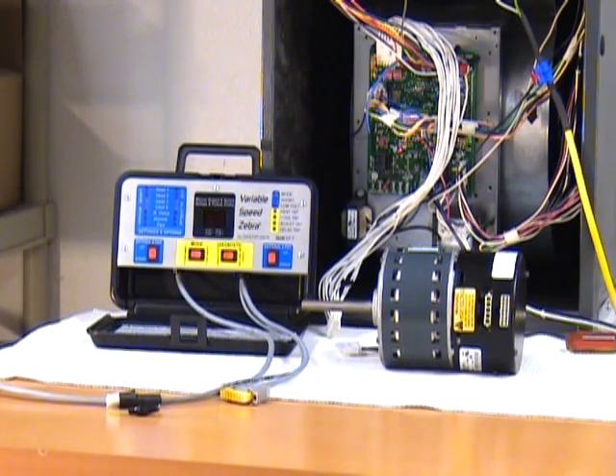GE makes an inexpensive tool, well, it's not terribly inexpensive, it's about 80 or 90 bucks, that just plugs into the motor. You hook it up and you turn on a switch, and they say if the motor runs on this one speed, the motor will probably run okay in all the other speed settings too, but they don't actually test any of those other speed settings. They don't give you any information about CFM and RPM. They don't allow you to monitor the signals coming from your furnace or air handler. And that's why the variable speed zebra was invented.